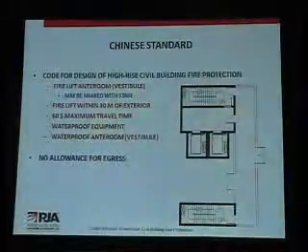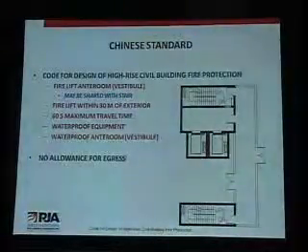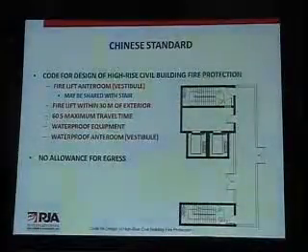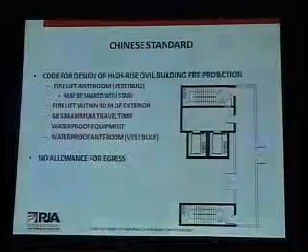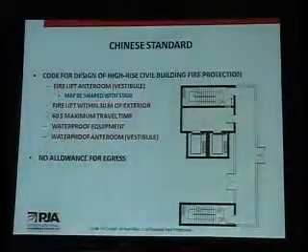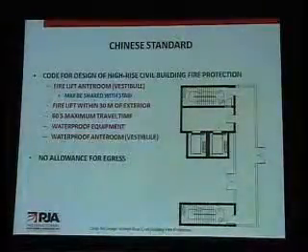Consistent with the European Union standards, there is the 60-second travel time and waterproof equipment. One unique requirement is that they have a requirement for waterproof vestibules. This is usually accomplished by just a raised landing in the vestibule to prevent any water that's discharged in the corridor from getting into that vestibule. Again, no allowance for egress.